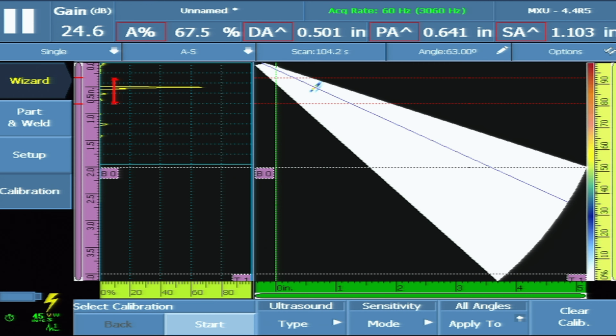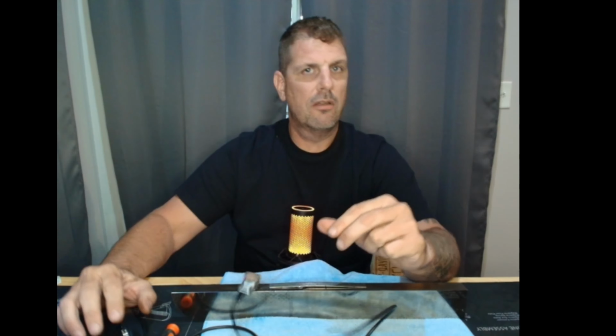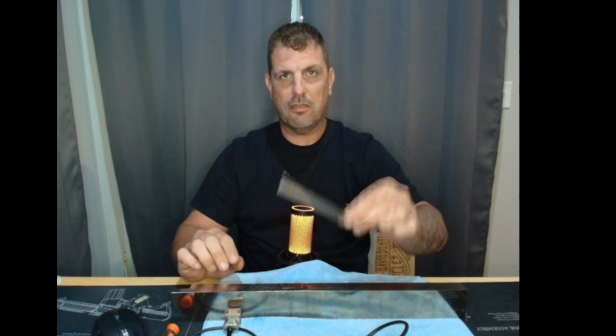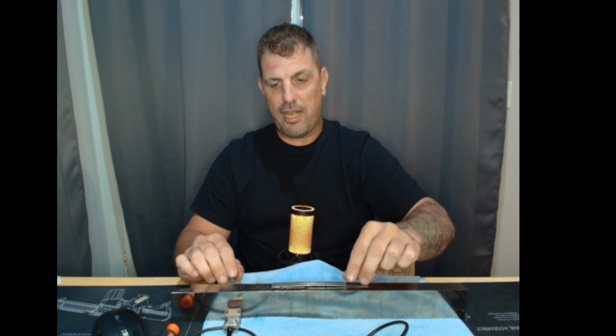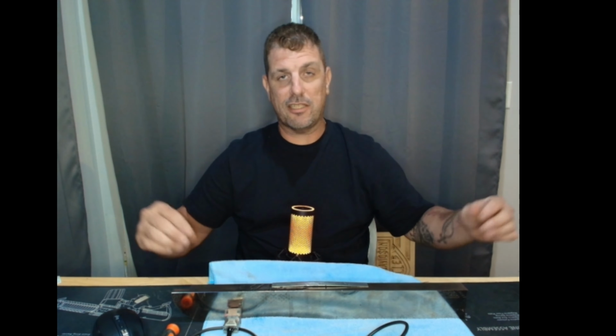Now we had a 1/2 inch is our hole. Now we're going to look at our PA. You look at your PA and your PA says 640. So you're going to come down and you're going to measure in front of your transducer and see if 640 is hitting that hole, which we are at 640. So we measured everything, 640 down and a 1/2 inch down. So that's it. You calibrated wedge delay and sensitivity. You're ready to move on to the next step. Y'all take care.